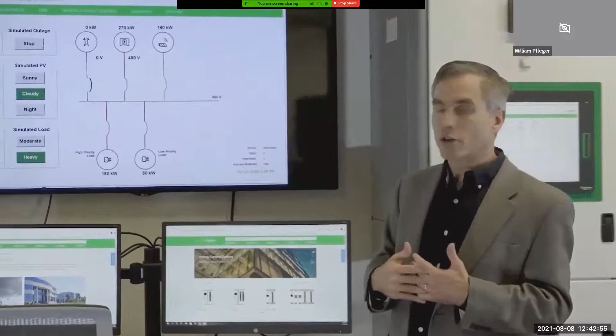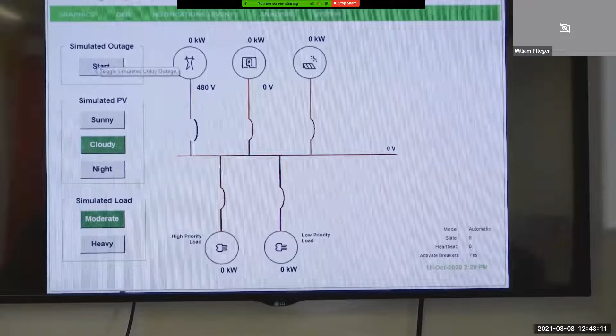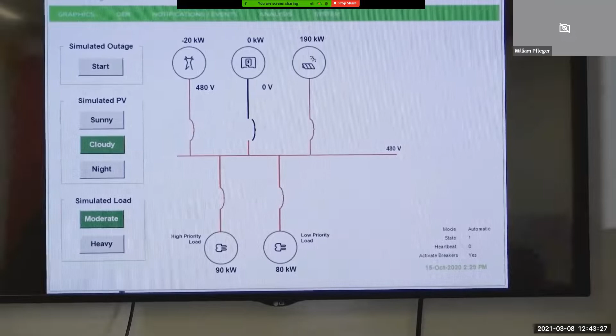Now, eventually, the utility is going to come back on. So let's go ahead and simulate that and witness how this particular system transitions back. So we'll stop our outage. Notice the utility at 480 volts. So we turn the generator off, open the generator breaker first, and then close the utility breaker in. And here we are back connected to the utility.